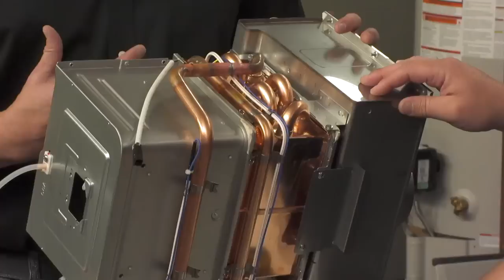And if you'll notice, it even comes back here and connects to the pipe on the back of the combustion chamber itself. Right there. And if that does open up, it's going to open the gas valve circuit, and it's going to prevent the heater from operating. It's a safety concern, definitely, at that point. So we need to make sure that we have that back on. If we do have to replace that heat exchanger, we've got that put back on, and it's put on properly.